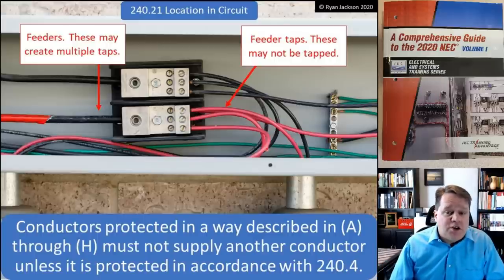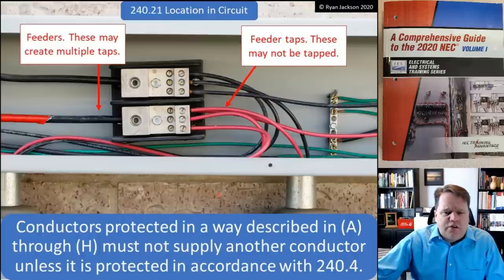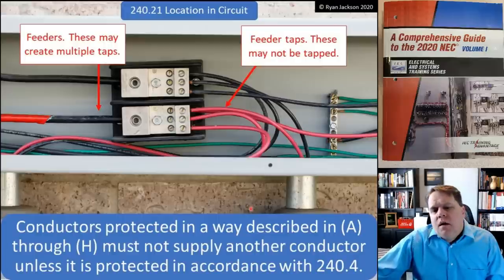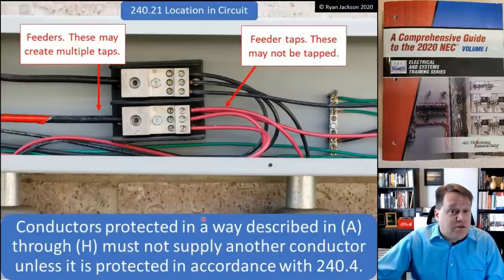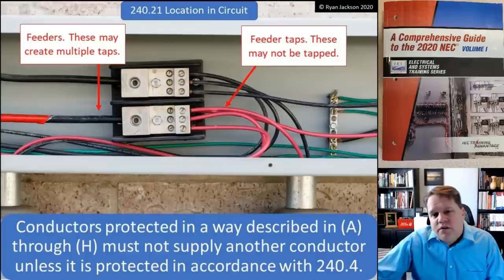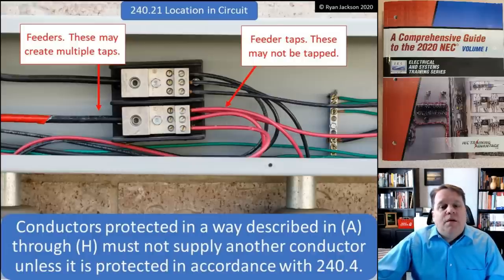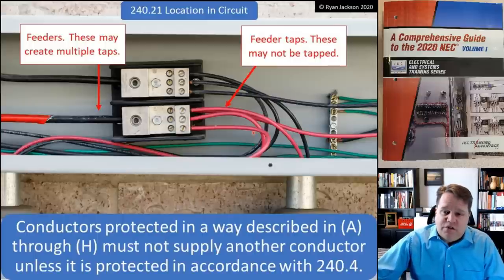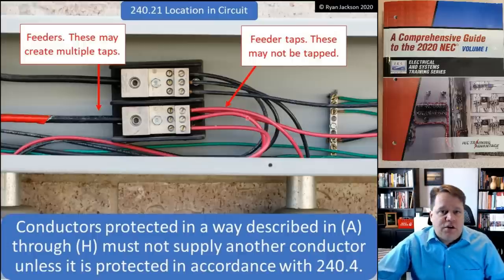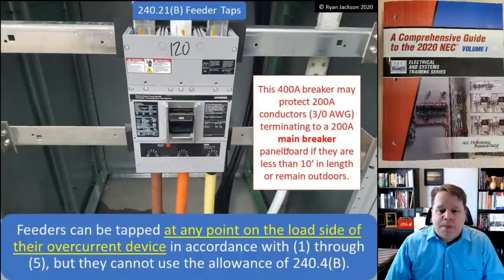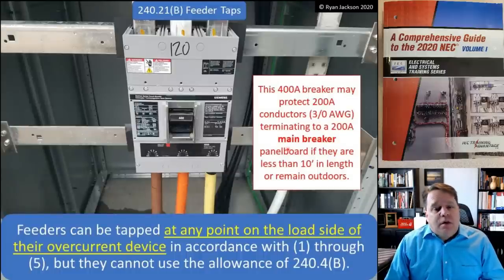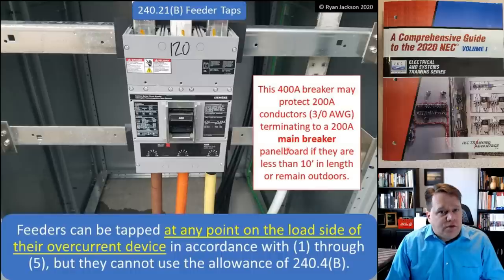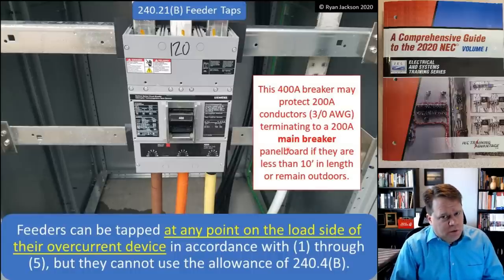The key rule is: you can tap the feeder as many times as you'd like, but you're not allowed to tap the tap conductor. For example, I couldn't tie onto an 8-gauge tap wire and run 14-gauge wire to a 15-amp fuse disconnect — that would be a violation because the tap cannot supply another conductor that isn't protected per the general requirements. A feeder can be tapped at any point on the load side of the overcurrent device.